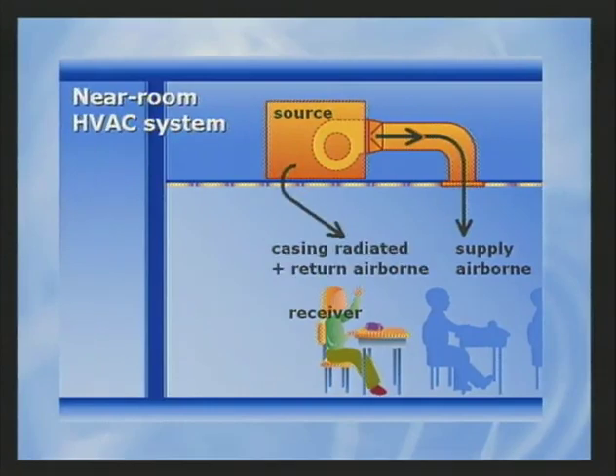Although ceiling tile can be very useful for its absorptive characteristics, it is not an effective barrier. If you choose to install the unit over a classroom, it's important to also provide an intervening barrier to attenuate casing radiated sound. Building a box around the unit can serve this purpose if the box is created out of a high transmission loss material like gypsum board and is well sealed.